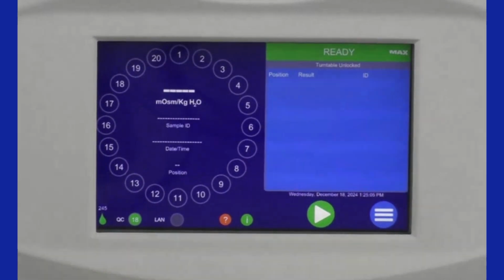The QC indicator is the next one to the right. It also has a number in the middle, which is right now an 18. That's because, remember, that 290 needs to be run every 24 hours at the same time of day each day, and I'll show you how to program that a little later. Right now the default on this instrument is 7 a.m., so I ran that QC at 7 a.m. It will count down each hour from 24 all the way down to when it will turn red, indicating that your Clinitrol 290 check needs to be run again.